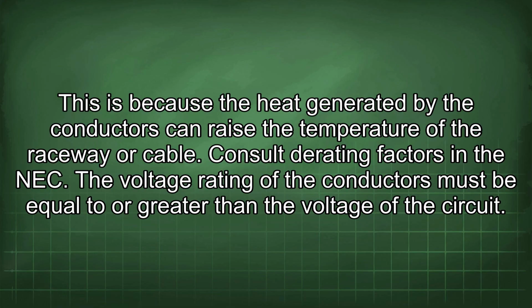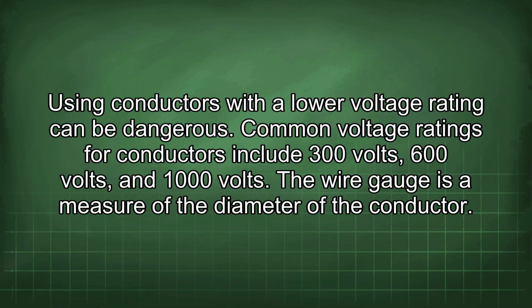The voltage rating of the conductors must be equal to or greater than the voltage of the circuit. Using conductors with a lower voltage rating can be dangerous. Common voltage ratings for conductors include 300 volts, 600 volts, and 1000 volts.